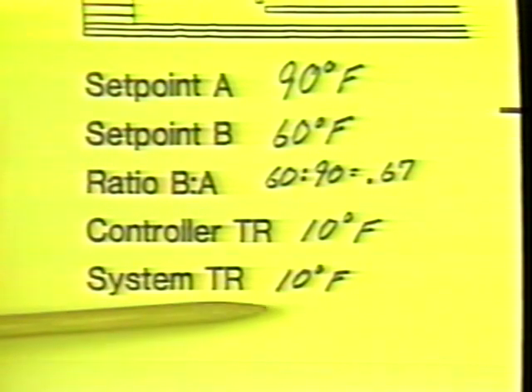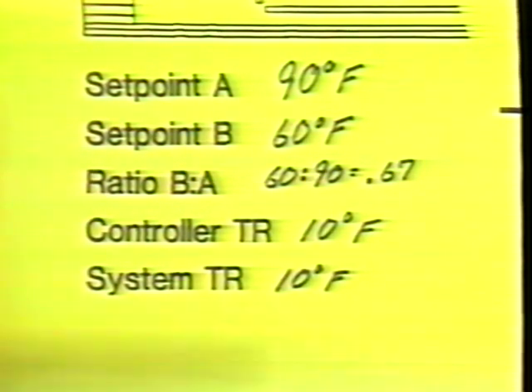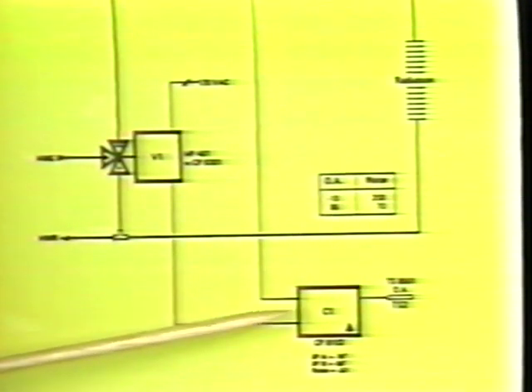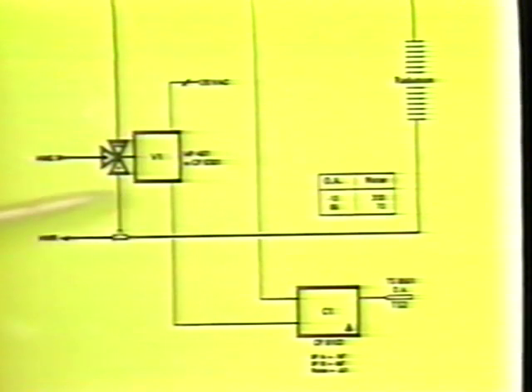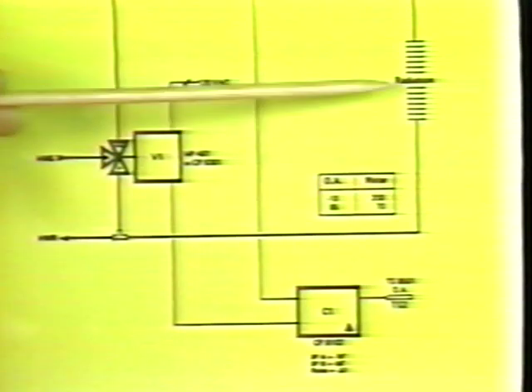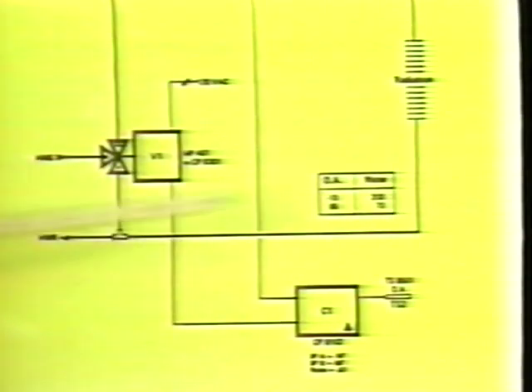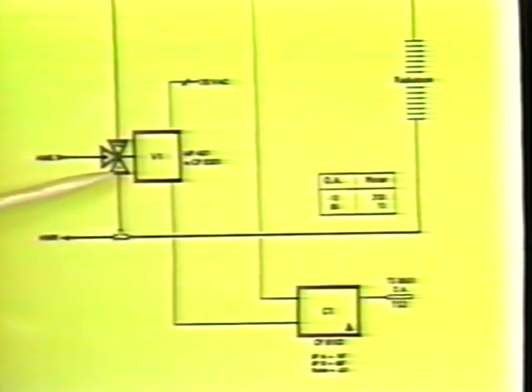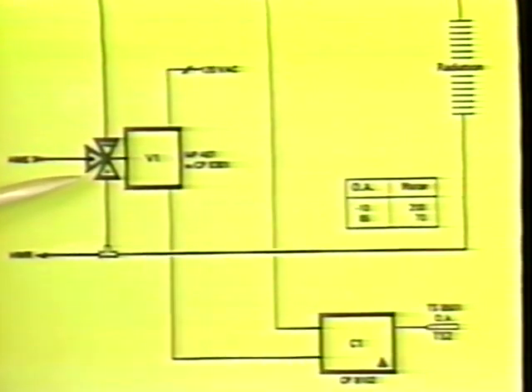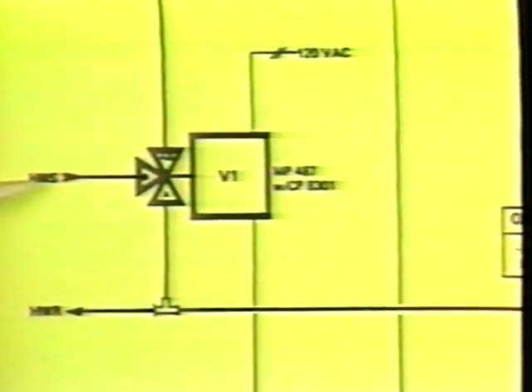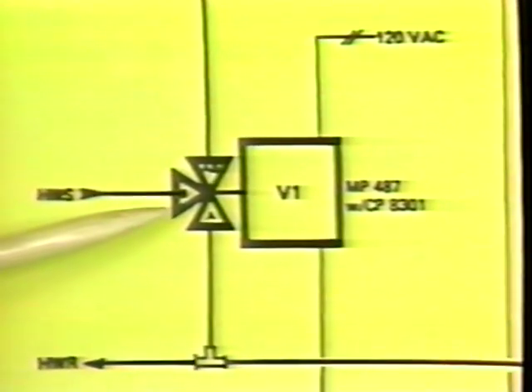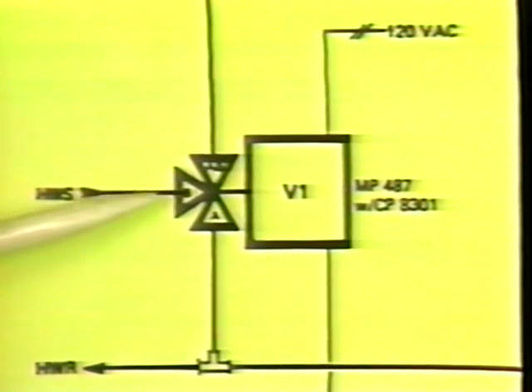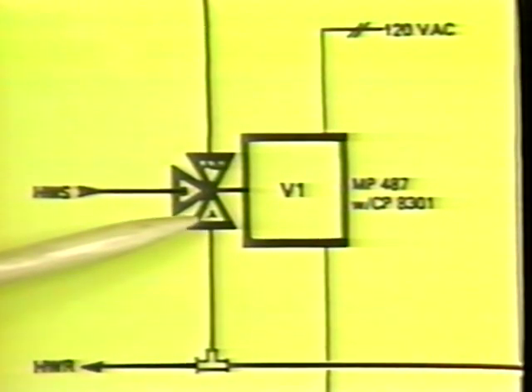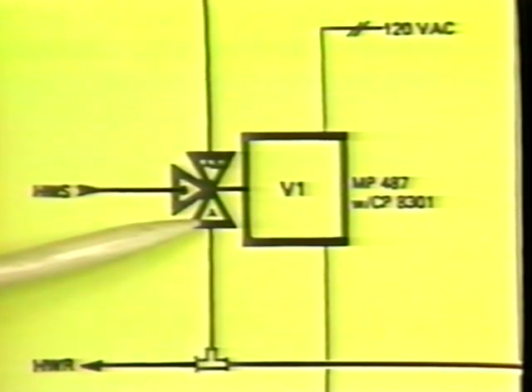Let's take a look at 2 examples of system layout. In this example, our CP8102 is controlling a 3-way hot water mixing valve, which in turn supplies water to finned radiation. With this valve, with no signal coming from the controller, our hot water supply, directly from a boiler or converter, is at 100%. In other words, this port is full open. This return water supply, or cooler water, will be fully closed.